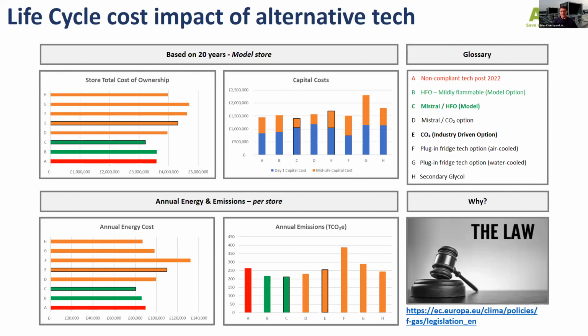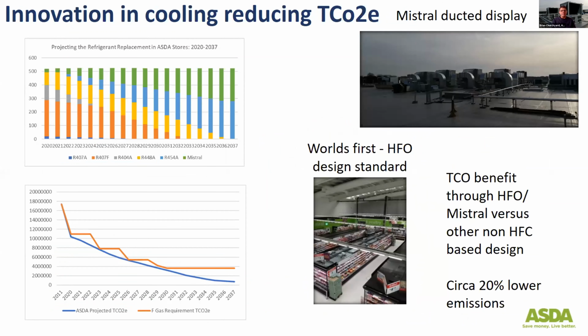So again, just reiterating that we are a technically agnostic business. We are led by the numbers, we are led by value, we are led by value to our customers. And that's really what drives our decisions and our choices within the regulation and also the requirements to reduce our environmental impacts. On this slide, more specifically, if you look at the F-gas regulation, which is the slide that Chris showed earlier, you can see the phase down of F-gas. To Chris's point, you get to a point eventually around 2040 where you need to be below 400 GWP average.